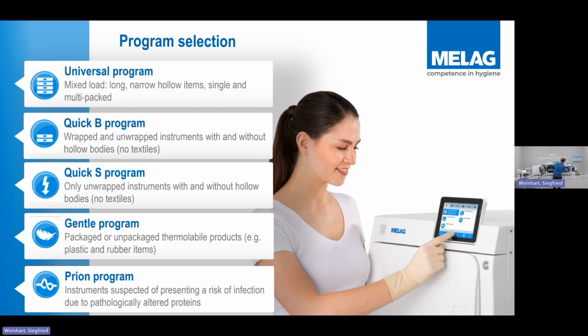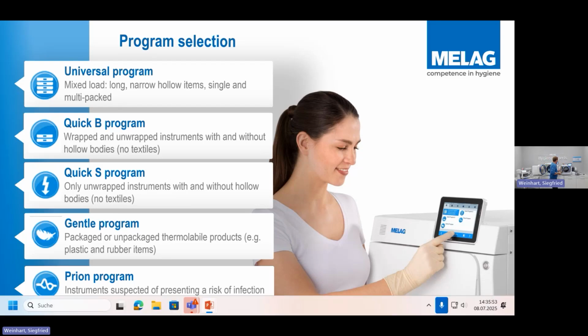You then got quick program B, which in essence would be that. Okay, it's what we call a half load. So that would be a half load of wrapped, or it could be 2 trays of wrapped at the top and 2 trays of unwrapped at the bottom, mixed load going in there, and that'll run that load. And most modern autoclaves will have these selections. You've then got your quick S, which is your typical day-to-day load. That is a full load of instruments. Unwrapped is always unwrapped, or the single wrapped solid instruments, but primarily unwrapped. Okay, and that generally would be your day-to-day cycle.